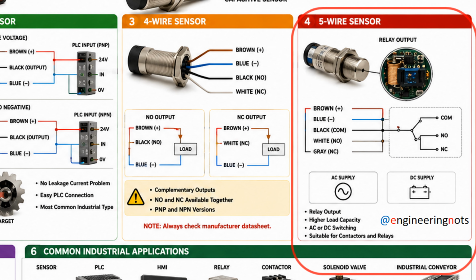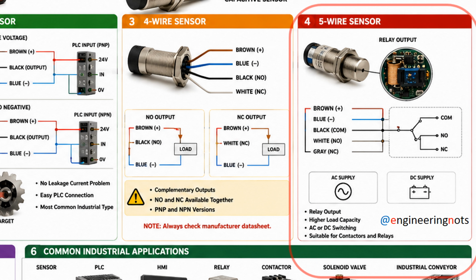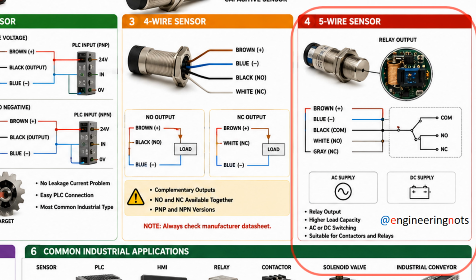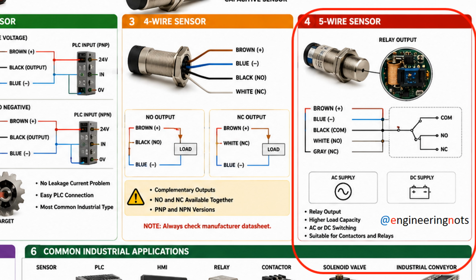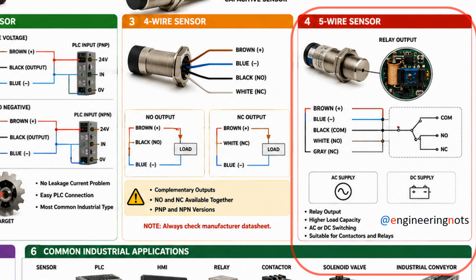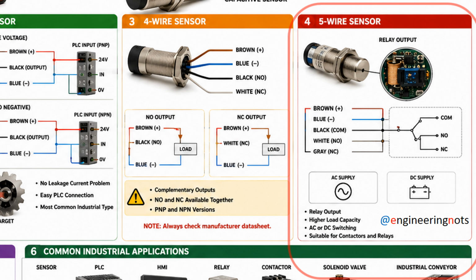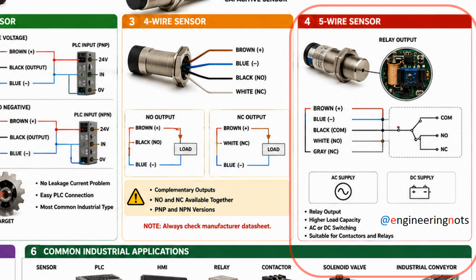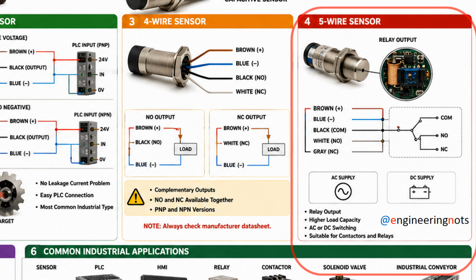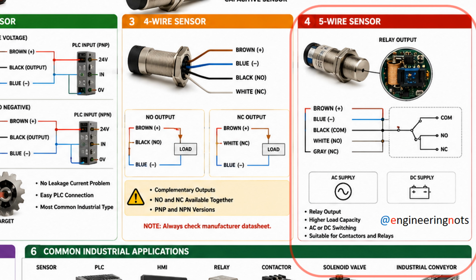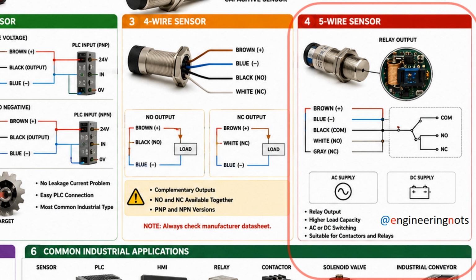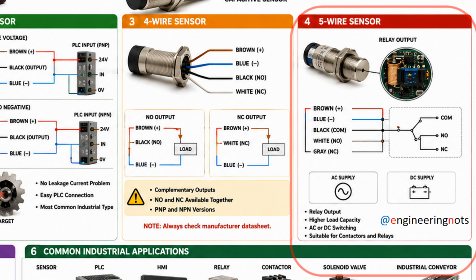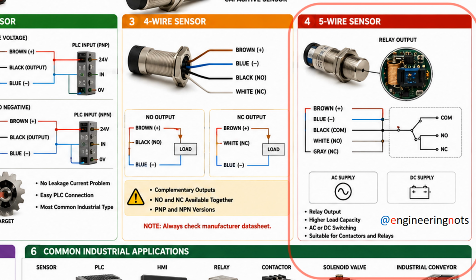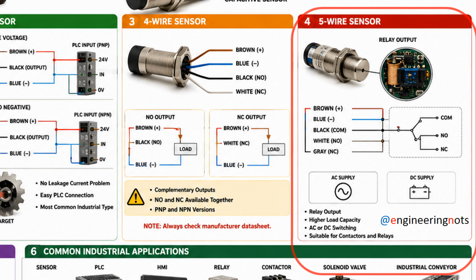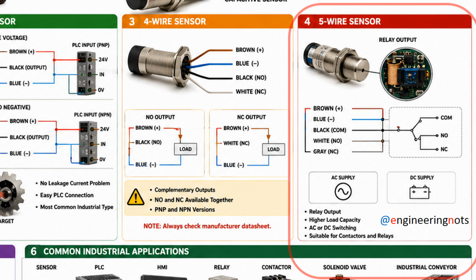5-wire sensors. Now we come to the most advanced group in this lesson, 5-wire sensors. The main difference is that these sensors typically use a relay output. Inside the sensor, there is a small relay. Because of this, the output behaves exactly like a mechanical contact. Terminals. 2 wires are used for the power supply. 3 wires are used for the relay output, including common, NO, NC.